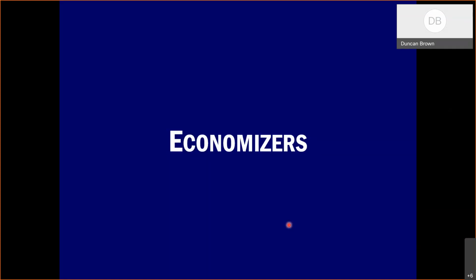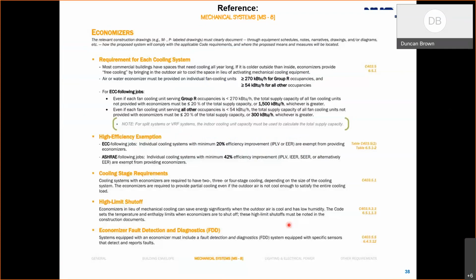So we're also going to talk about economizers very briefly. They were a big part of the 2016 code that people had a lot of difficulty complying with. And in the 2020 code, this was updated to be less stringent for residential buildings. Next slide, please. So with the 2016 code, the limit was 300,000 BTUs. And then with the 2020 code, this changed to 1,500,000 BTUs for residential buildings. Next slide, please.